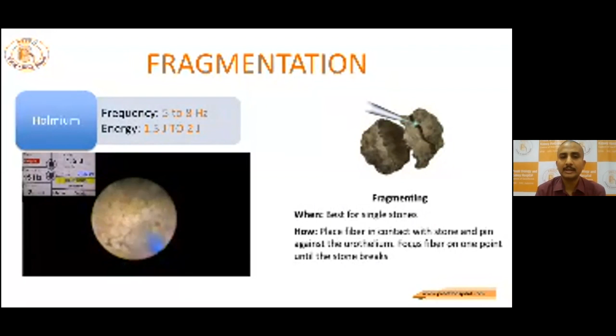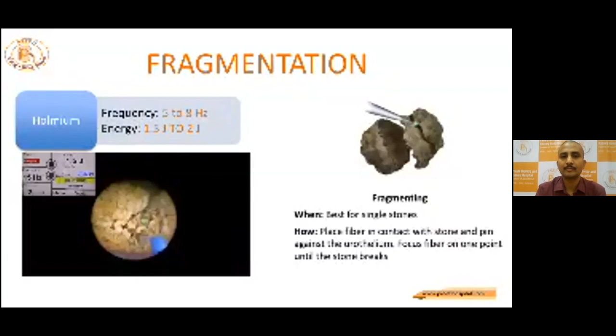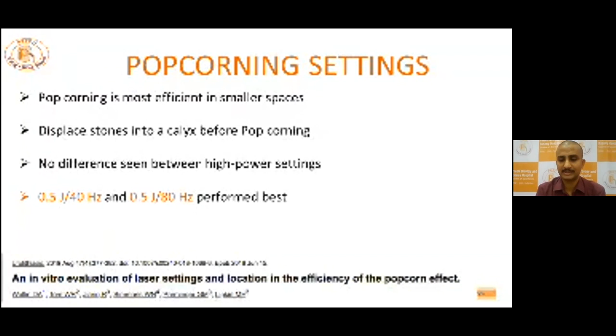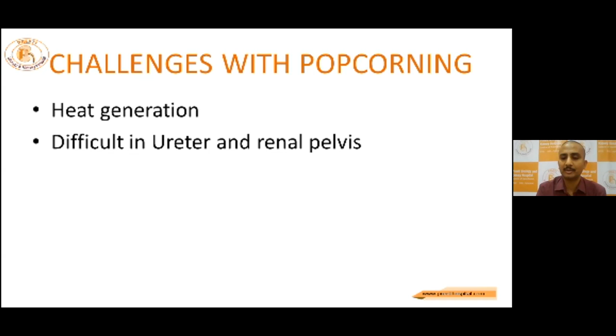Fragmentation, we commonly use it for the bladder stone, where we can extract the fragments or make them into multiple small pieces and extract them. Energy is 1.5 to 2 joules and frequency is 5 to 8 hertz. For popcorning settings, it is the most efficient in smaller spaces. Displace the stone into a calyx before popcorning, and no difference is seen between the high power settings. The challenge with popcorn is we can't do it in the ureter or in the renal pelvis. You have to push the stone into a calyx, and because of the multiple vibrations at the frequency, there is heat generation.